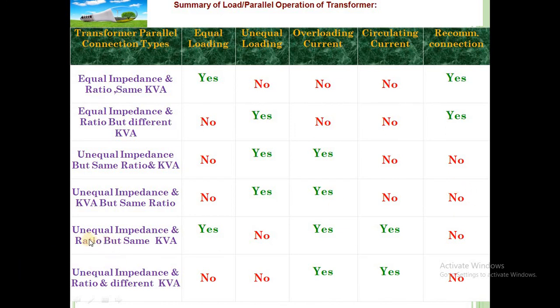Now next is unequal impedance and unequal ratio but same kVA, means impedance आणि impedance चा ratio हा unequal आहे but kVA is same. So what will happen? Equal loading will be there, unequal loading will not be there, but overloading current will be there. So this overloading current is mainly due to the unequal impedances. Now circulating current, there will be a circulating current and it is not a recommended connection, means when two or more transformers are connected then if this condition is there, then there will not be any parallel operation carried out.